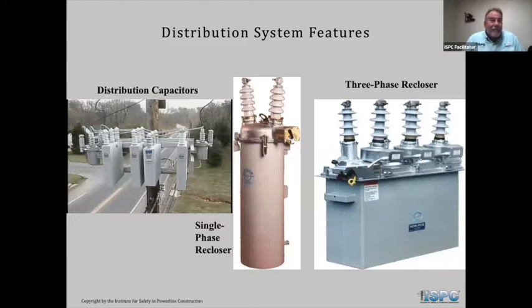Capacitor banks. Um, the big hazard with the capacitor banks is grounding. They actually hold a charge, and they help increase the current that reduces the effects of motor load. So, for instance, if you had 7,000 volts on a single phase line, and we had 6 or 8 motors, like maybe a dry cleaner or something, 6 or 8 motors going, it would actually drop the voltage down a good bit. So a capacitor actually helps increase the amperage, the current on the line, so that the voltage can stay up for regular customers.